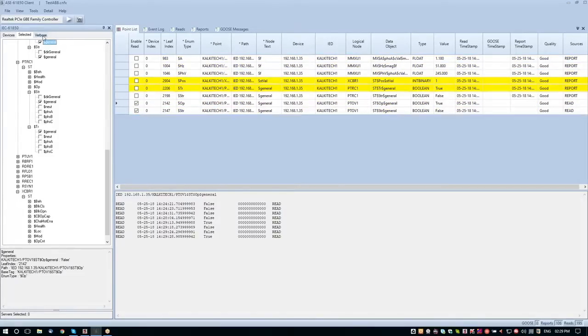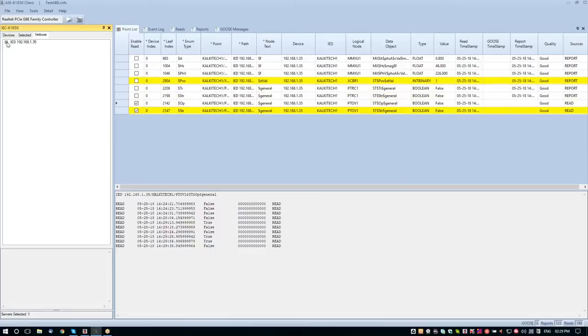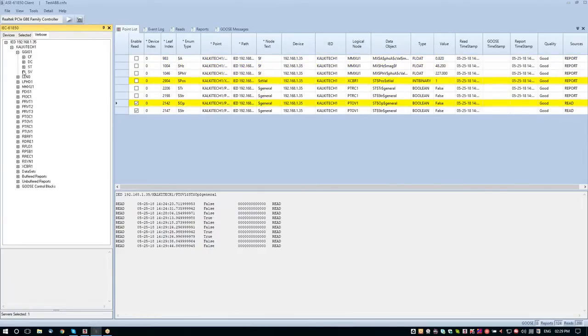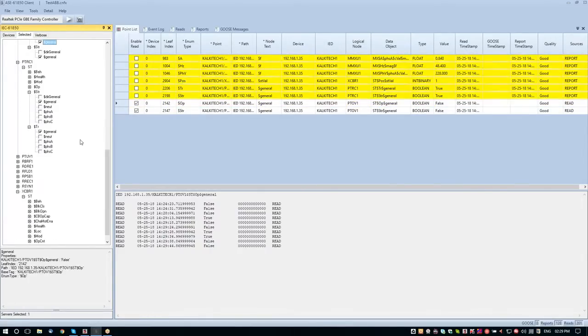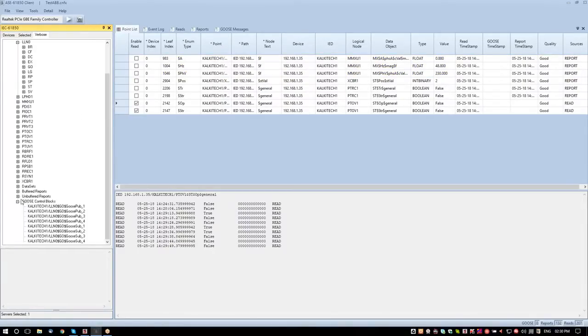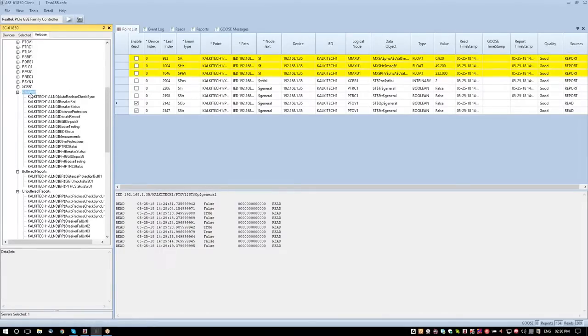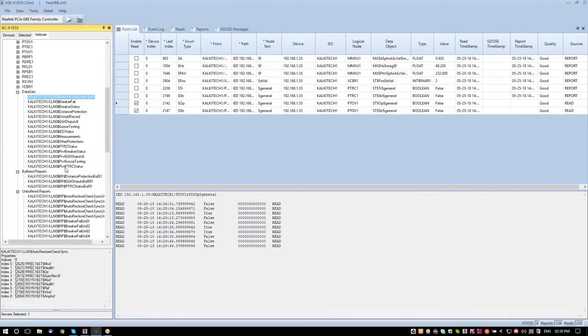Control operations can be performed by going into the third pane on the left-hand side. By selecting the third tab, there is a detailed view of data points available. In the second tab, it basically gives the list of status and measurement values. Those can be added to the point list. Under the verbose tab, there are more options available, which include the listing of GOOSE control blocks, buffered and unbuffered report control blocks, datasets of the report, and data points associated with the dataset can also be viewed in the bottom pane.